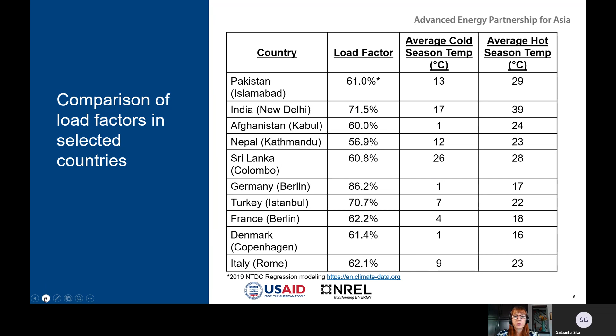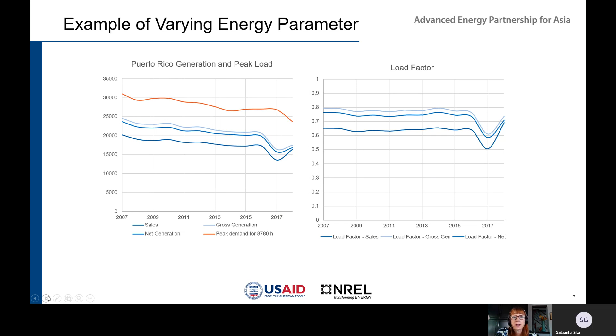To give you an example of how the parameter you choose for the numerator, the annual generation number, will impact the result, I show in Puerto Rico's case how utilizing either sales, net gen, or gross gen can influence the level. The generation and peak load are here on the left graph, left axis, and then when you calculate the load factor, they're all the same relative to each other, but you have quite a different result, 80% down to 65%, depending on what number you grab. Next slide, please.